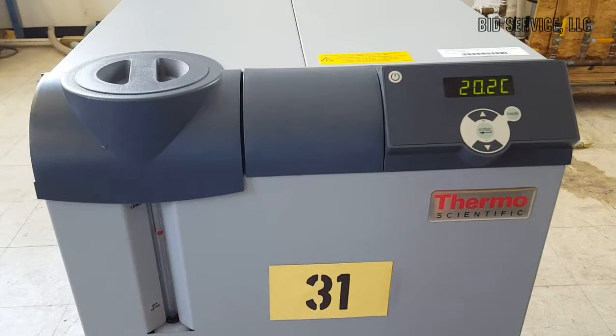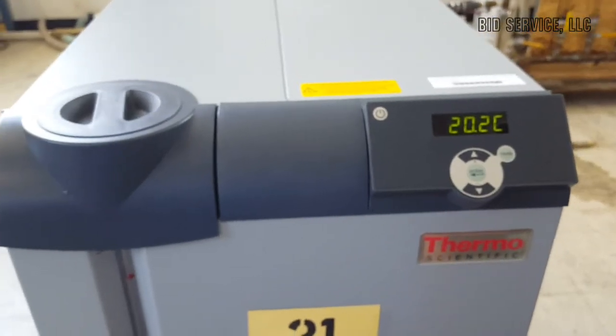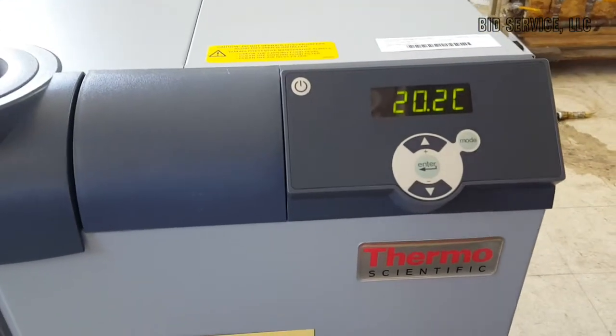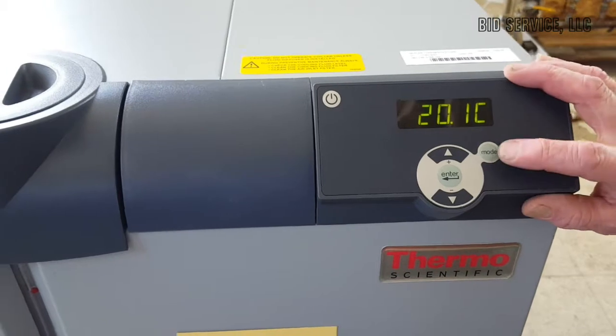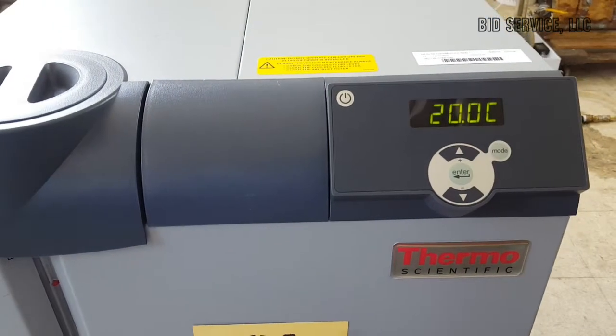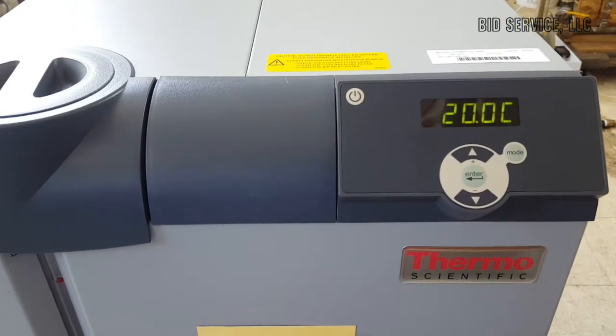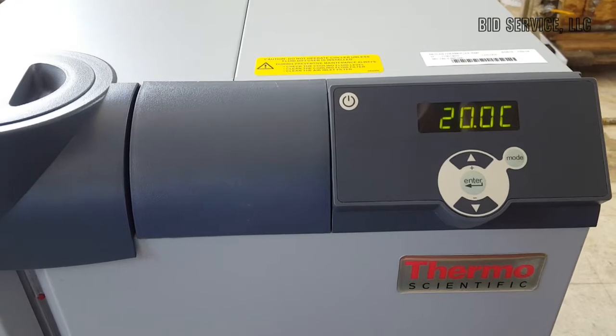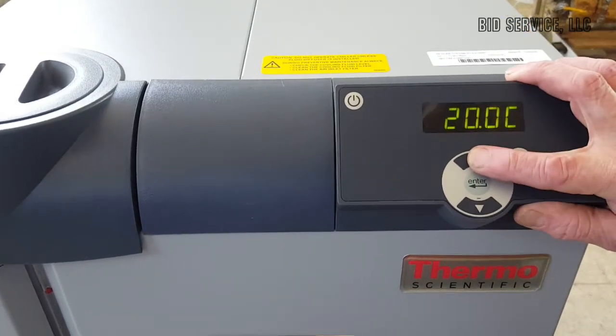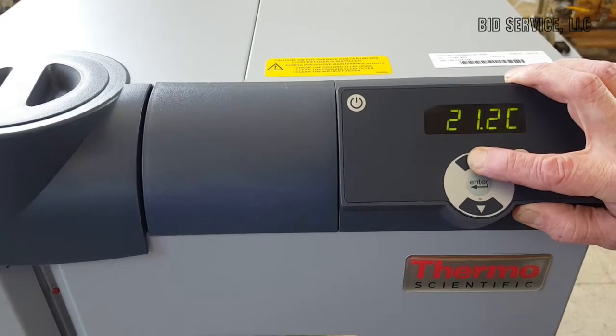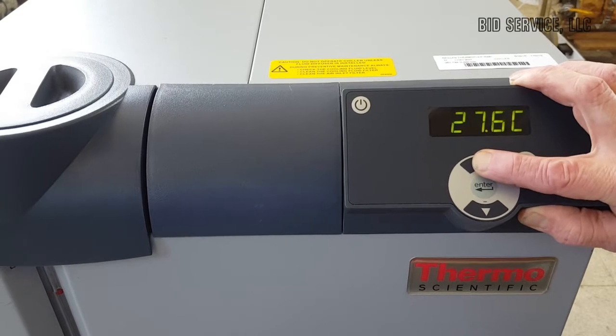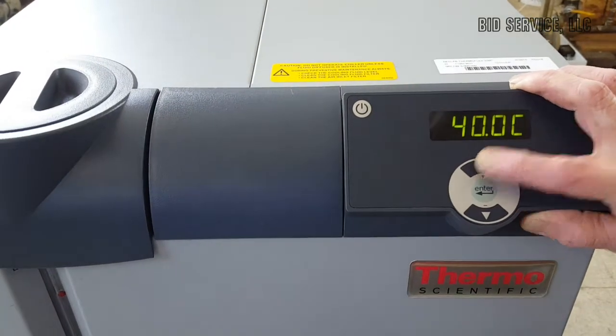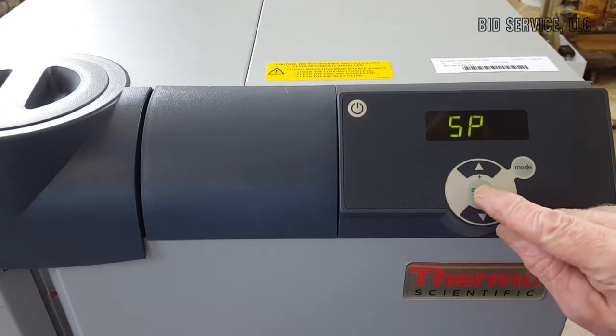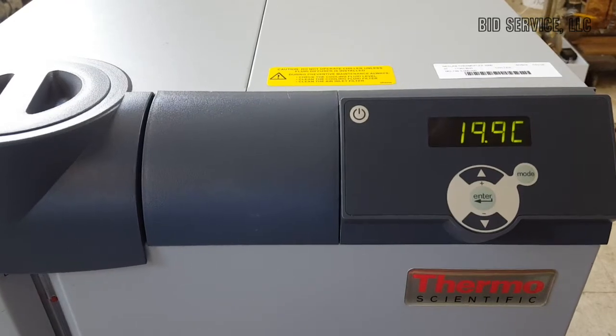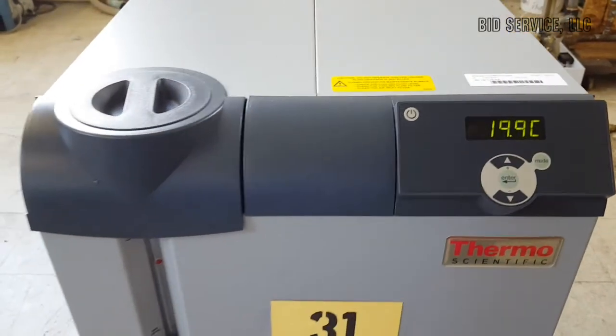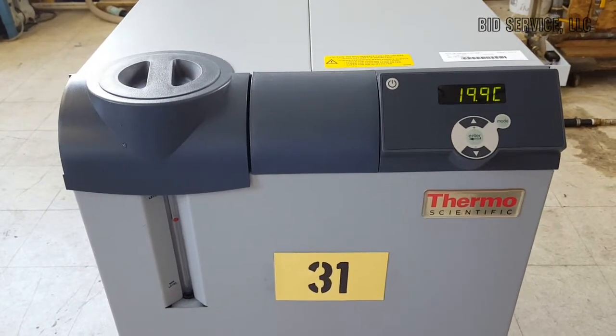The controller is one of the simplest ones I've seen. It's wonderful. The manual itself has instructions on how to use the different modes, but for purposes of our demonstration, we're going to show you how to change the set point. Now, if we push mode, you'll notice that it's blinking, and SP stands for set point. Again, this has a range of from +5 to +40. So first we're going to heat it up, and we're going to go all the way up. Now once you get to your set point, you press enter, and there you go. Now this will start to go up in temperature very shortly, so we'll come back in a little bit and see how we're doing.